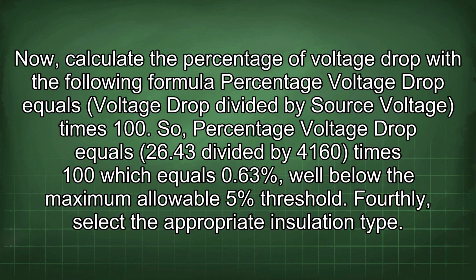Now calculate the percentage of voltage drop with the following formula: percentage voltage drop equals voltage drop divided by source voltage times 100. So, percentage voltage drop equals 26.43 divided by 4160 times 100, which equals 0.63%, well below the maximum allowable 5% threshold.